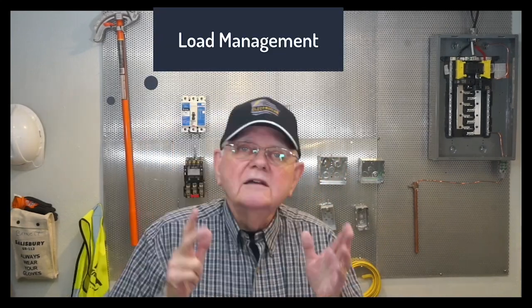And what it talks about is breakdown of insulation on the ungrounded conductor, and then that other grounded conductor that could cause a ground fault. And so anyway, now we have a definition for likely to become energized. Then load management. The idea of load management, we see more and more of this, don't we? We need to what?